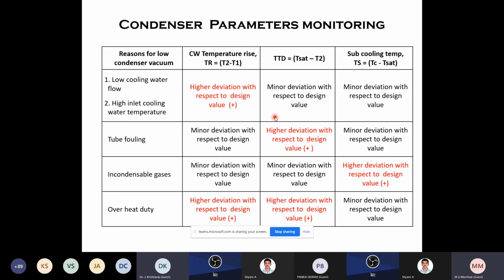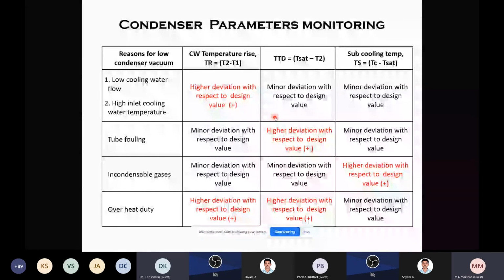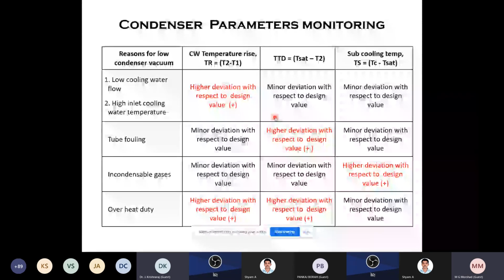for the low vacuum condition, because the majority of low vacuum conditions are due to partial loading. When the vacuum is low, we have to reduce load. Condenser cleaning is not very easy. First, you have to establish for what reason, and only after that can you do it. It can be done during performance checking of the condenser also. Those who are doing performance checking on a monthly or half-yearly basis can very well take this data and monitor it very easily. It will be very easy to understand and to carry out the exercise.